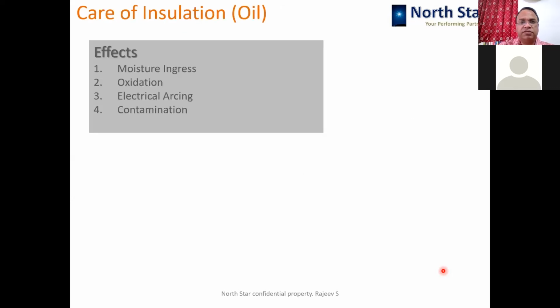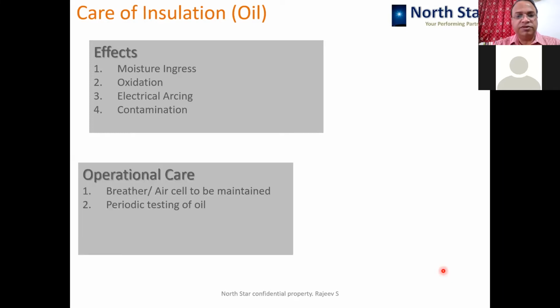So in the case of insulation oil, when we talk about liquid insulation, how is it different from solid insulation? Liquid insulation is easy to manage because you can remove the moisture ingress, the effect of oxidation and other contaminants by way of filtration. So you can very easily filter the oil and make it as good as new. And if filtration is not enough, then you can go for reclamation and regeneration of the oil. So managing liquid insulation is much easier compared to solid insulation.